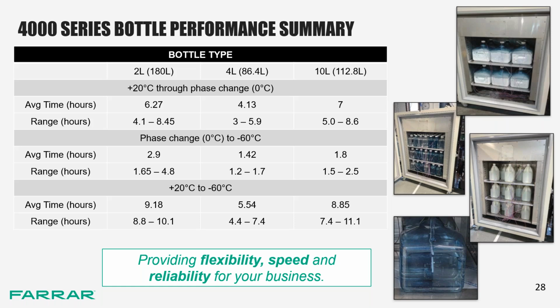We also fit 24 4-liter bottles, or just over 86 liters, into the chamber and froze those bottles to minus 60 between 4.4 and 7.4 hours. And finally, we took 12 10-liter carboys totaling over 112 liters and froze them to minus 60 between 7.4 and 11 hours. These results also tell a slightly different story.